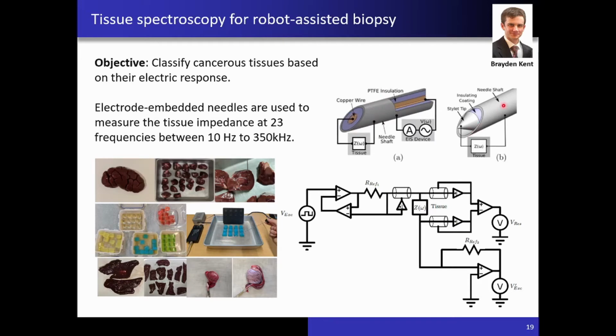The second configuration is seen here. The needle shaft acts as one of the electrodes, and the stylet is an insulating material, and only the tip is exposed. So here we have one of the electrodes, here we have the other one, and this arrangement allows the stylet to be removed from the needle, freeing the shaft so that drugs or radiation can be delivered.